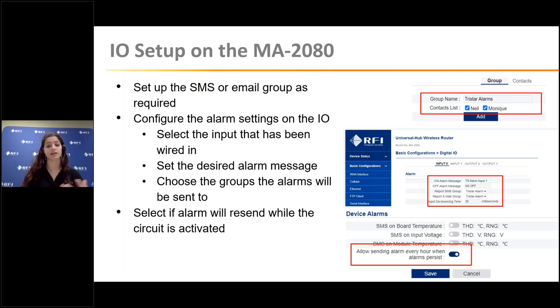From there, you look at the setup for the basic configuration of the IO itself. You can customize a message, which is a nifty feature in the MA2080 - not all IO allows for customizable messages. This means we get something more exact than just saying IO0 has been triggered; we can fit quite a few characters in a single text message. In this case I've said 'TriStar alarm input 1', giving more context for the message sent out, making it easy to be interpreted by people, not just machines.